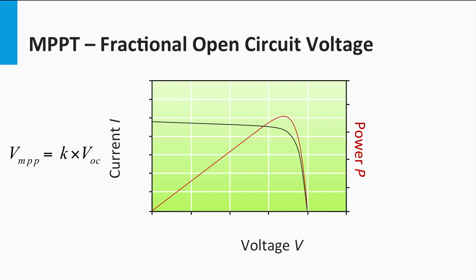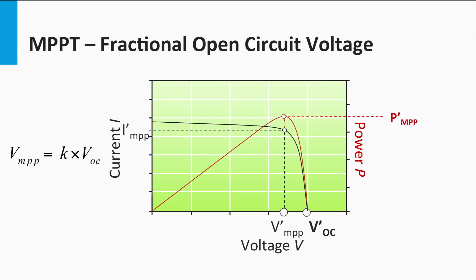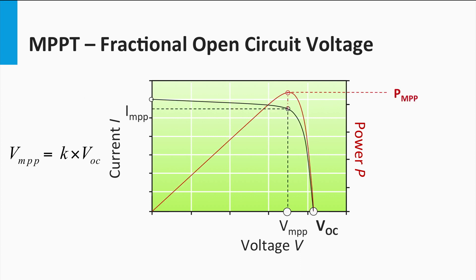How does the MPP tracking device measure the open-circuit voltage of a solar module under operation? This is done by disconnecting the PV module from the load momentarily — in other words, the PV current is set to zero so as to measure the open-circuit voltage. Although temporary, this results in a loss in production of PV power, and this handicap only worsens if this measurement has to be made more frequently.